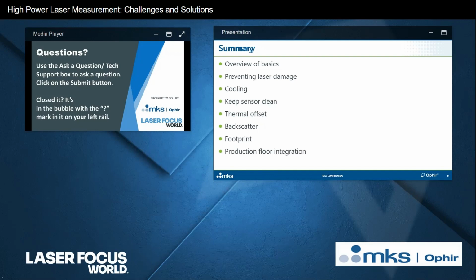Okay, so in summary, we talked very briefly about the basics. We talked about preventing laser damage, and I'll just mention again, turn on the water flow and bring it up to speed before you turn on your laser. Bring the laser power up gradually. Watch the cooling water flow specs that the manufacturer gives for what the sensor needs. Keep the sensor clean, much better than having to have it repaired.